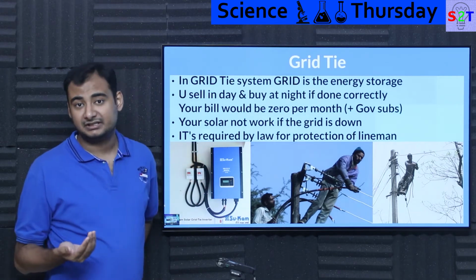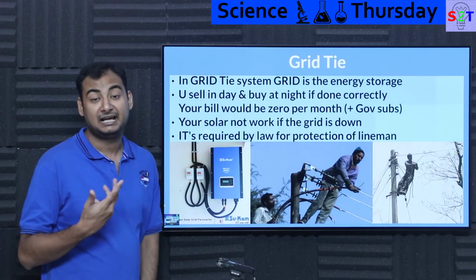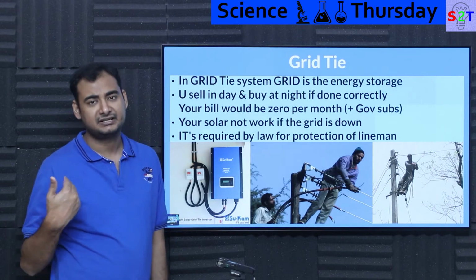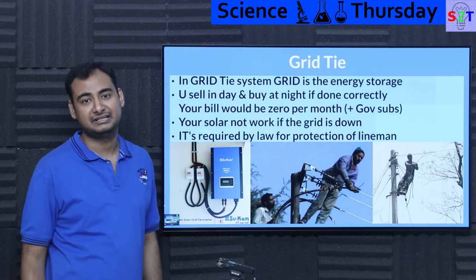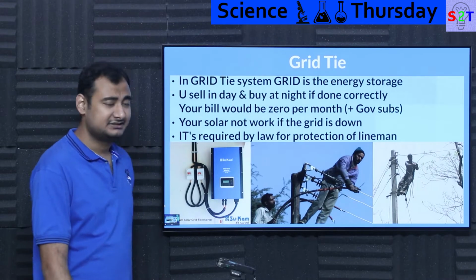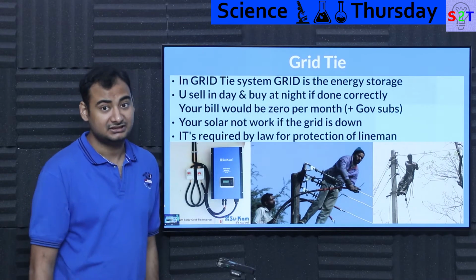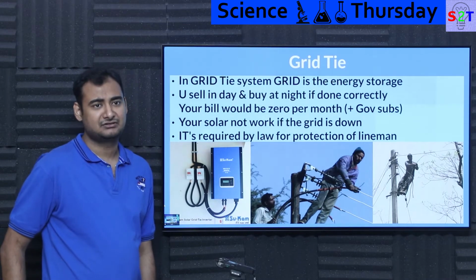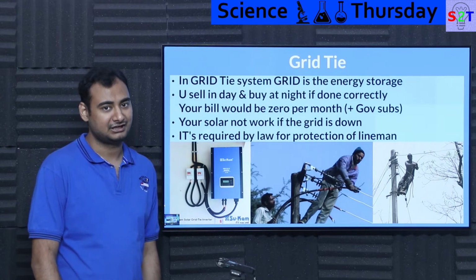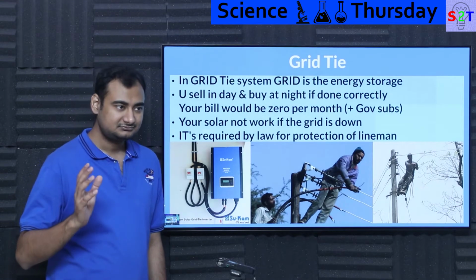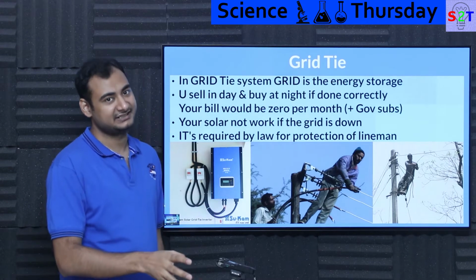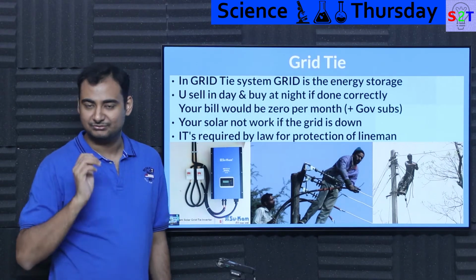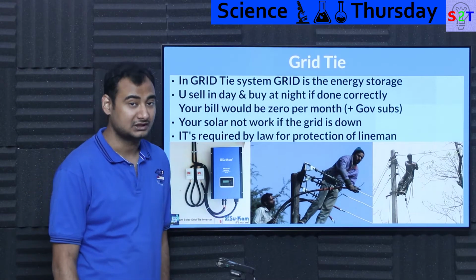So is there a way to run a grid tie inverter in island mode, so to say? Yes, you need a disconnect and a way to trick the inverter into thinking it's connected to the grid. It's not very easy, and that's why it's not done that often. Many inverter companies will flat out void your warranty if you try something like that. So it can be done, but if the company says it can't, do not try to circumvent it, because you may end up in a scenario where things don't work out.